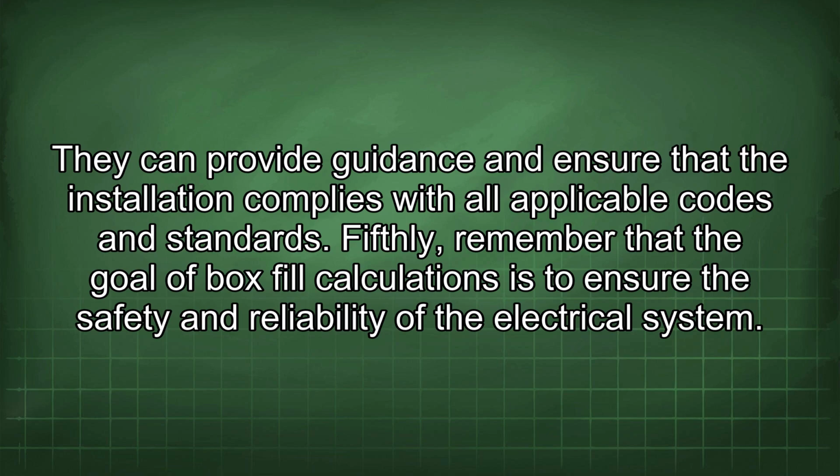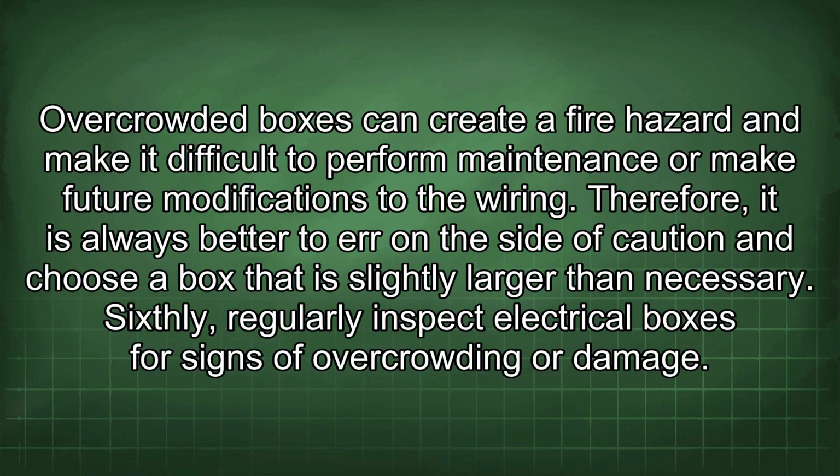Fifthly, remember that the goal of box fill calculations is to ensure the safety and reliability of the electrical system. Overcrowded boxes can create a fire hazard and make it difficult to perform maintenance or make future modifications to the wiring. Therefore, it is always better to err on the side of caution and choose a box that is slightly larger than necessary.